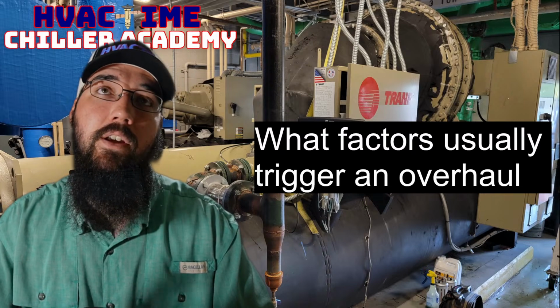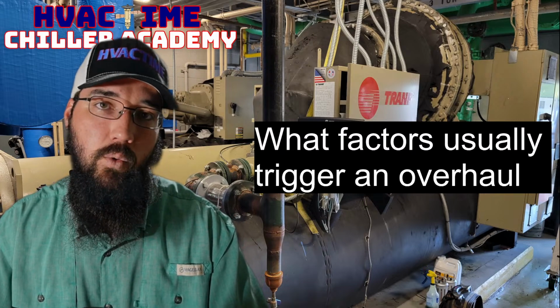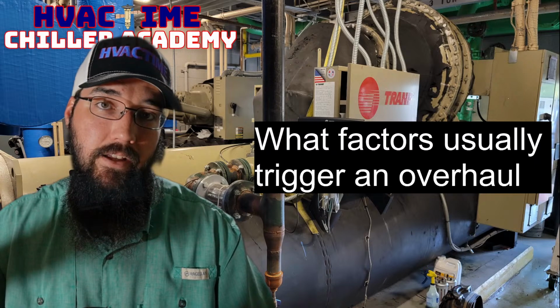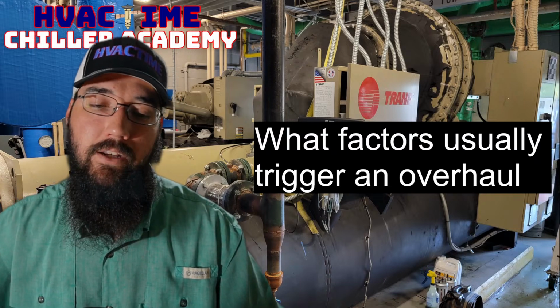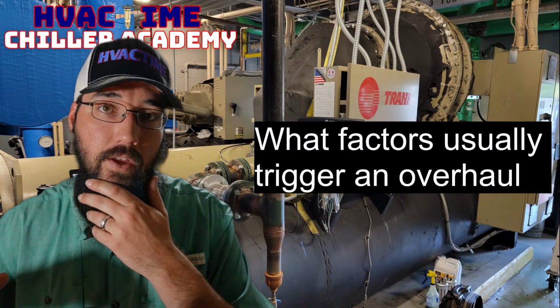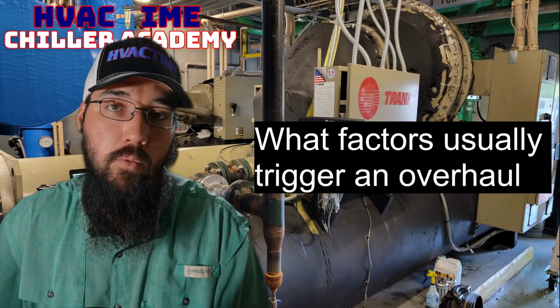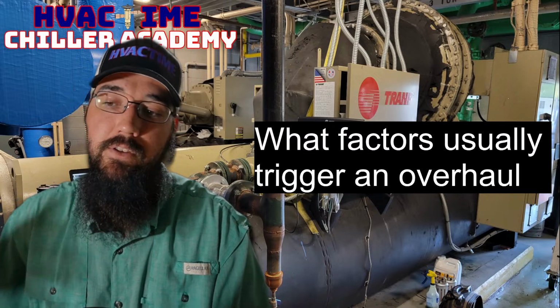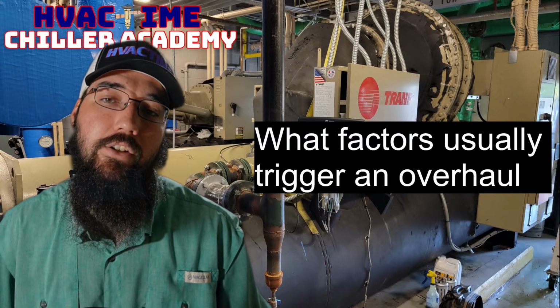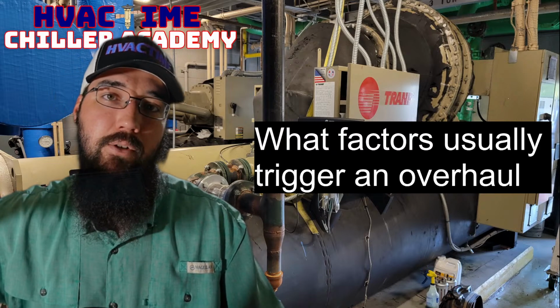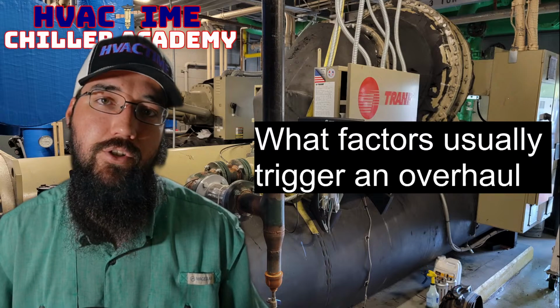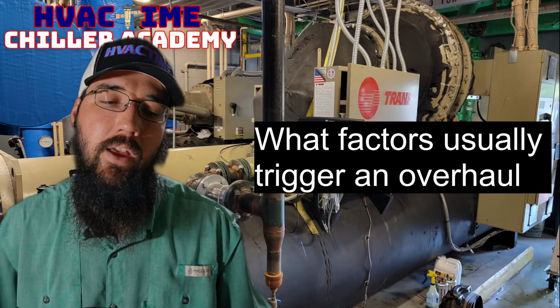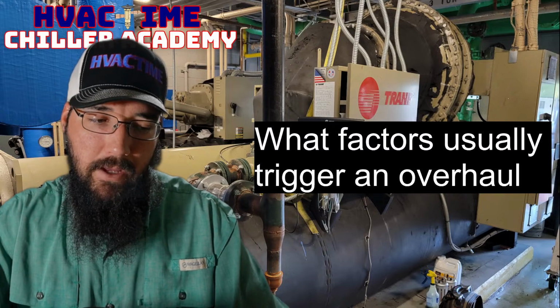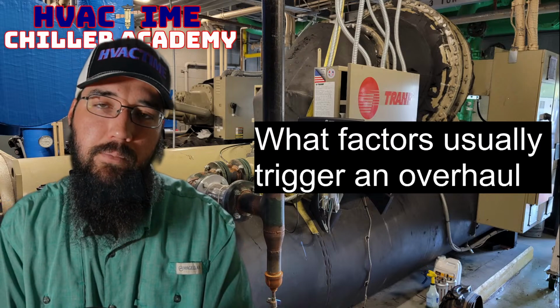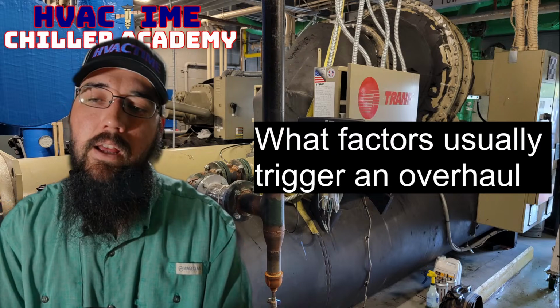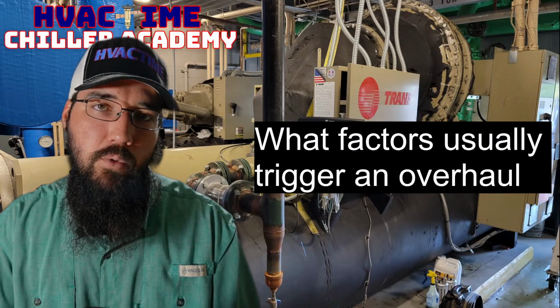Or in the event of the impellers getting tore up, you'll have issues maintaining lift. You'll get into these really low lift conditions where under normal circumstances you'd run just fine, but the compressor just can't do it. As soon as it begins to build lift at all, it starts having surge issues. In the most extreme cases, a tore up impeller, whether from touchdown or from liquid, that's going to show more symptoms of that.